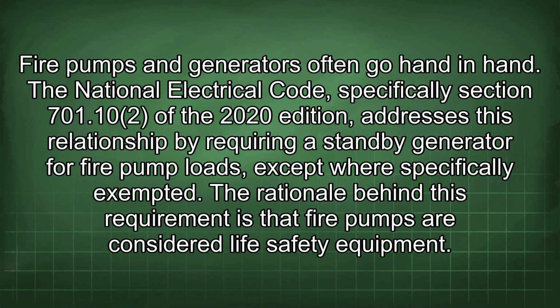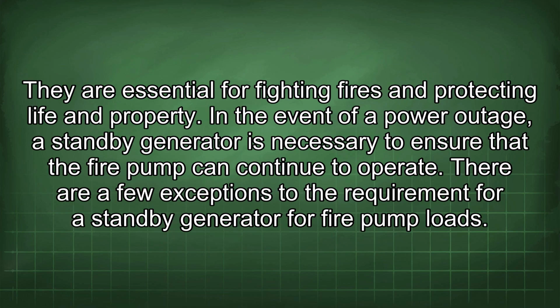Fire pumps and generators often go hand in hand. The National Electrical Code, specifically Section 701.10 of the 2020 edition, addresses this relationship by requiring a standby generator for fire pump loads, except where specifically exempted. The rationale behind this requirement is that fire pumps are considered life safety equipment. They are essential for fighting fires and protecting life and property.